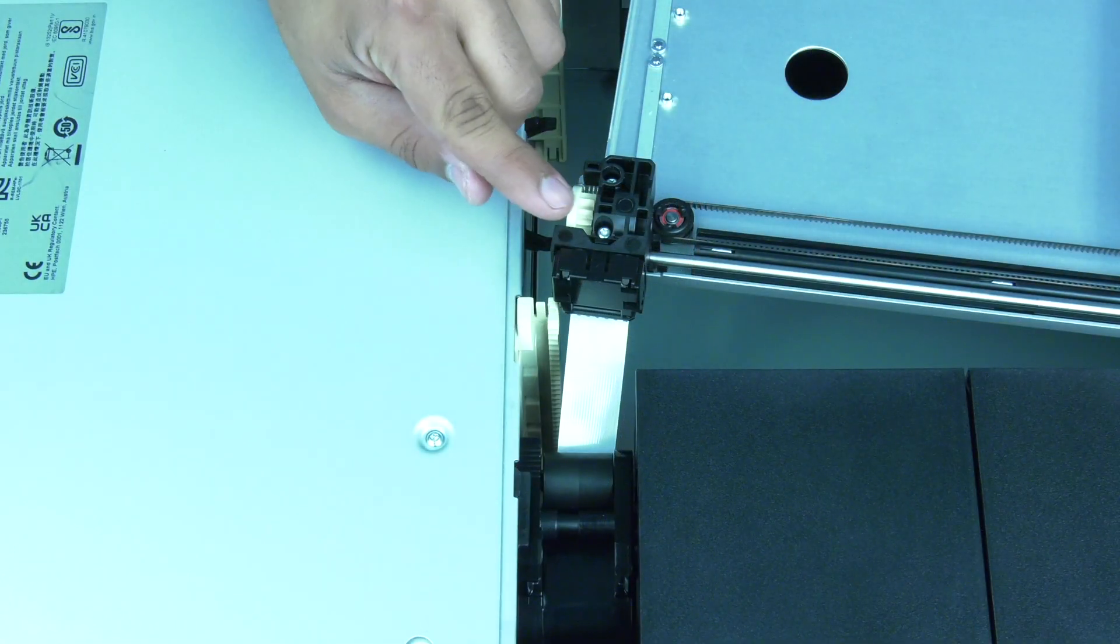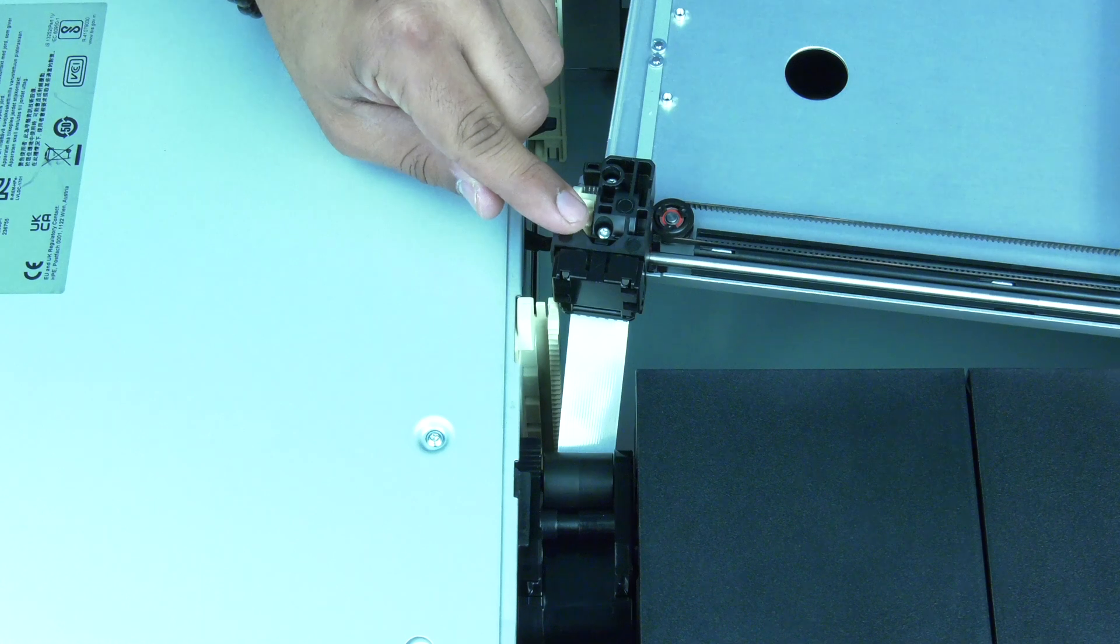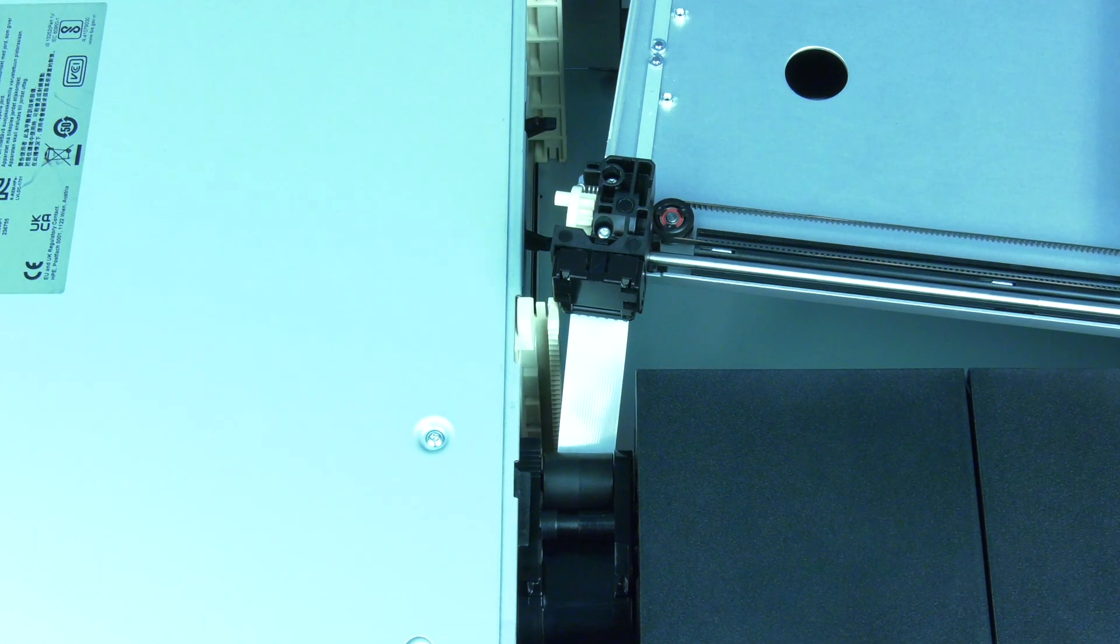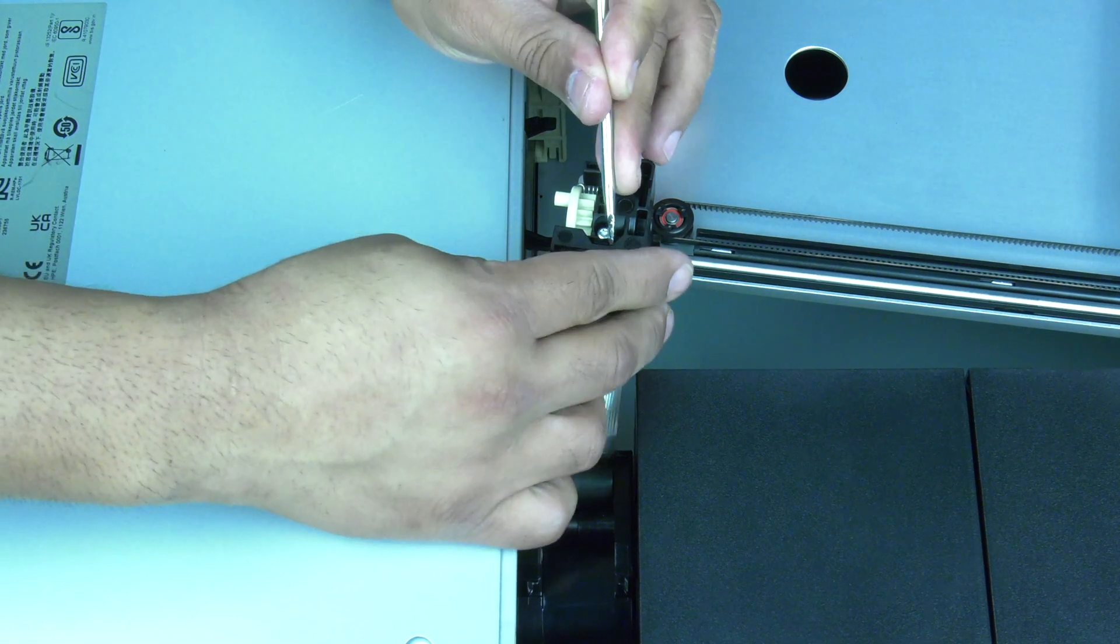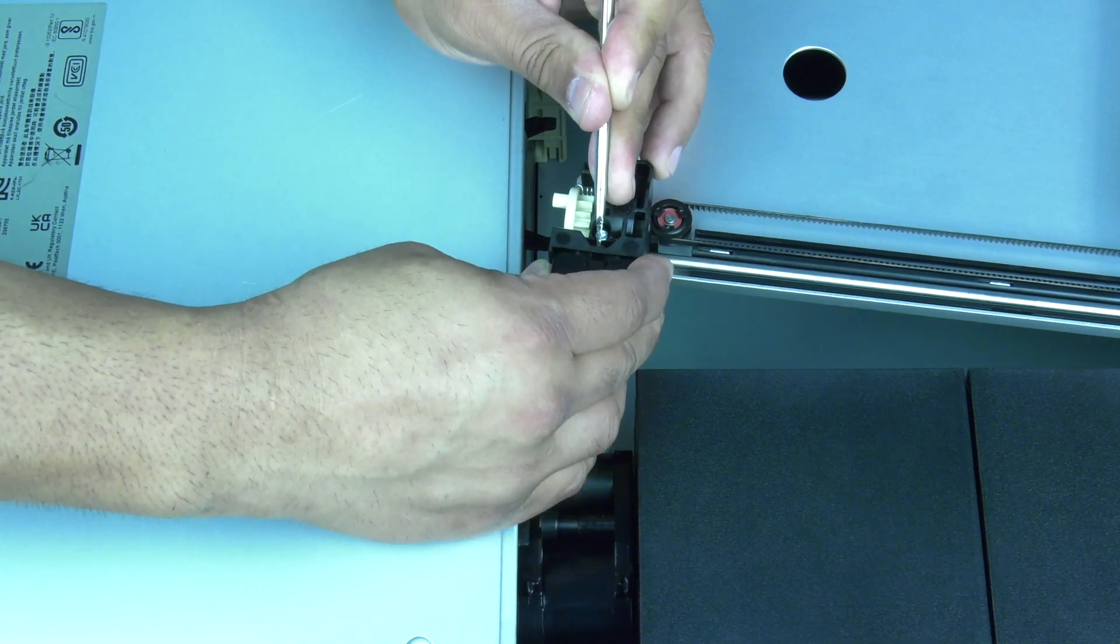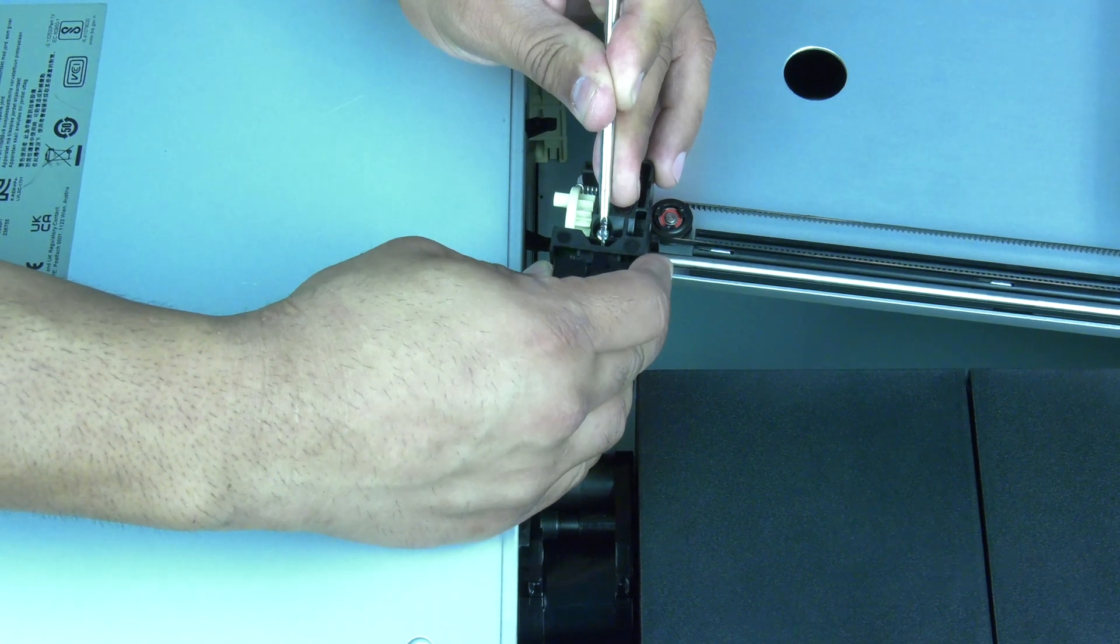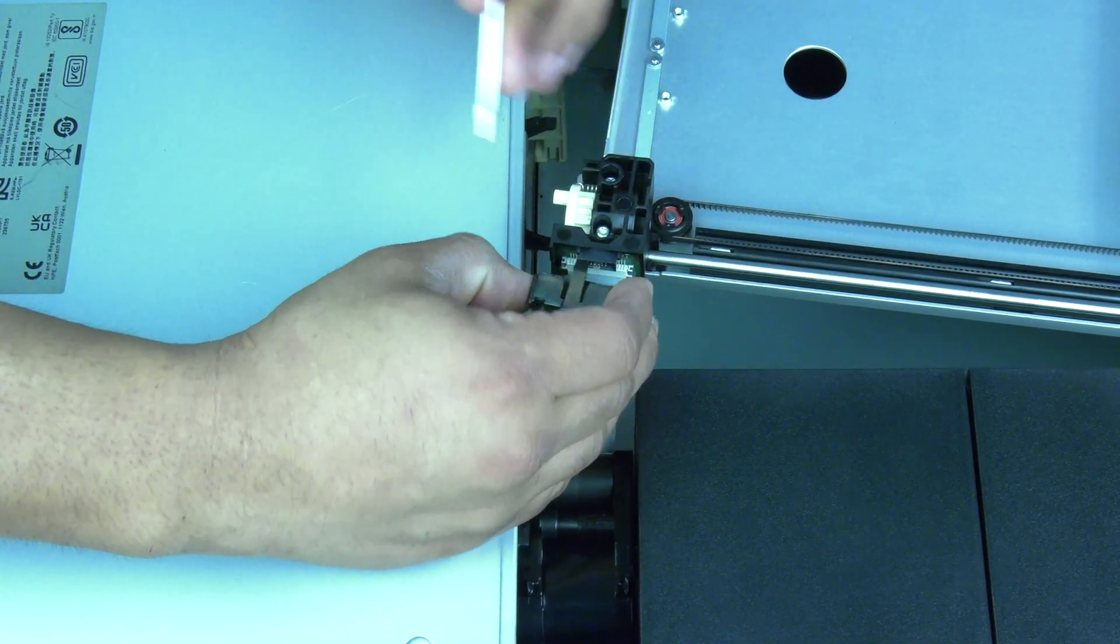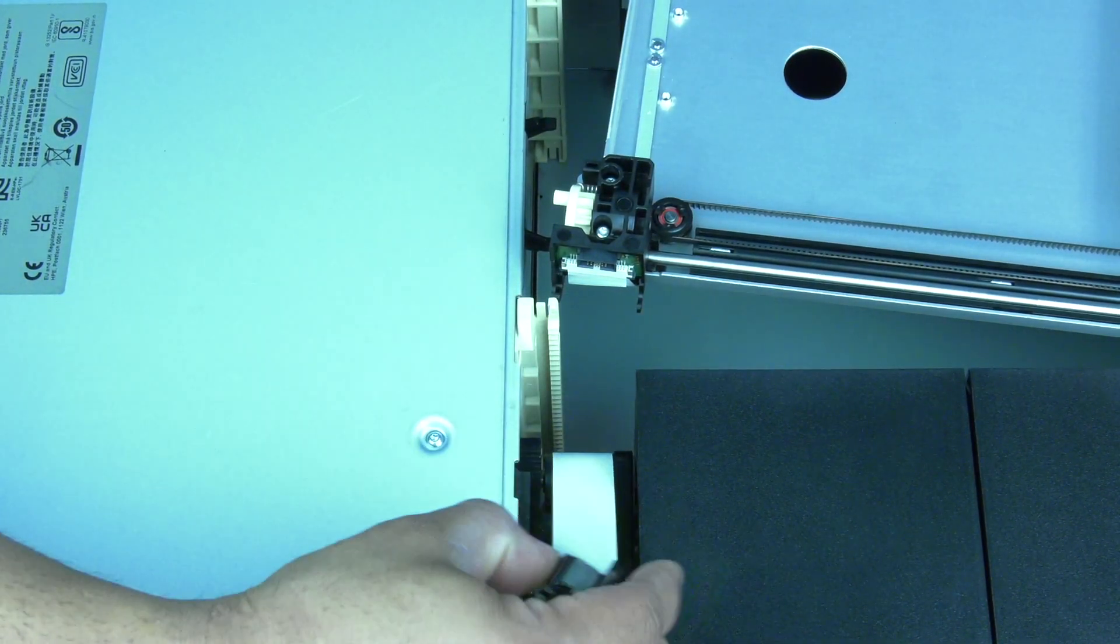Now on the top of the robotic assembly where the picker cable is attached, you will need a small flat head screwdriver to push the small latch that locks the picker cable to the picker. After you push the latch in, you can pivot the connector downwards and unhook it and allow it to safely retract into the cradle on the spooling mechanism.